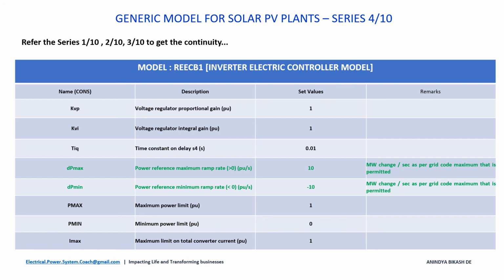So other parameters like Pmax, Pmin, this is the default parameter. So it is the maximum case, it is in per unit. So whatever is the plant maximum capacity, based on that you can put it as 1 per unit.